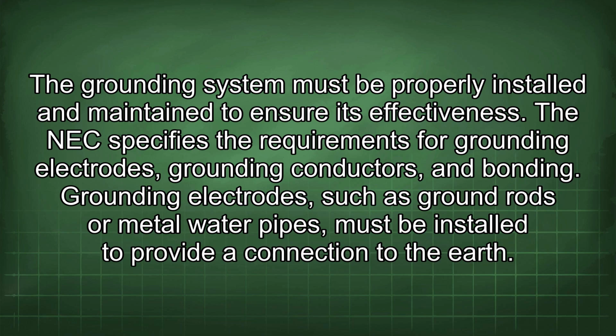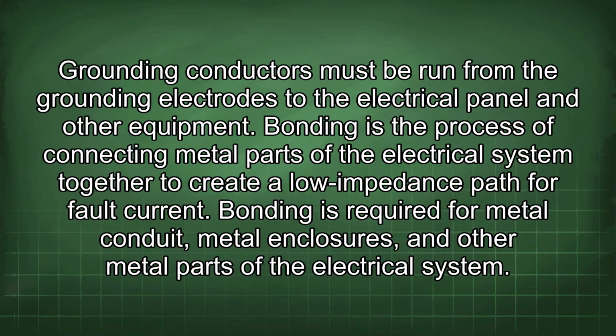Grounding electrodes, such as ground rods or metal water pipes, must be installed to provide a connection to the earth. Grounding conductors must be run from the grounding electrodes to the electrical panel and other equipment. Bonding is the process of connecting metal parts of the electrical system together to create a low impedance path for fault current. Bonding is required for metal conduit, metal enclosures, and other metal parts of the electrical system.